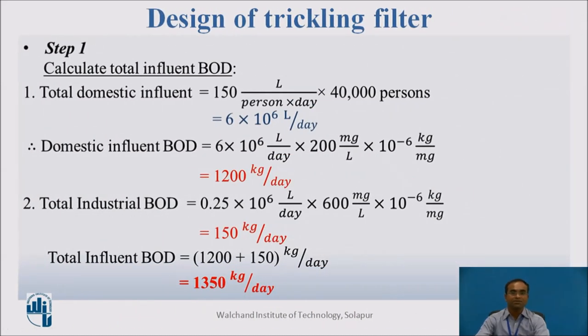Step 1: Calculate the total influent BOD. First, calculate the total domestic influent: 150 liters per capita per day multiplied by 40,000 persons gives 6 × 10⁶ liters per day (6 MLD). The domestic influent BOD is 6 MLD × 200 mg/L × 10⁻⁶ kg/mg, giving 1,200 kg per day.